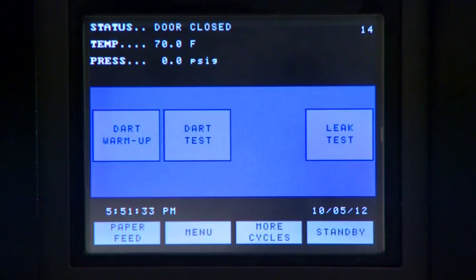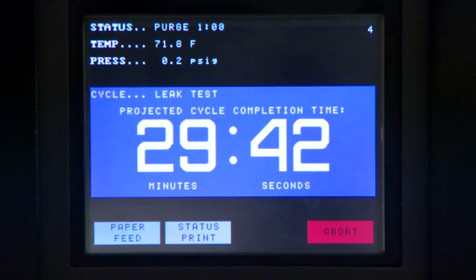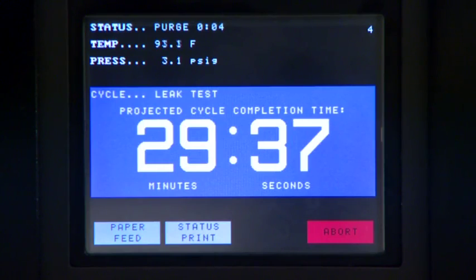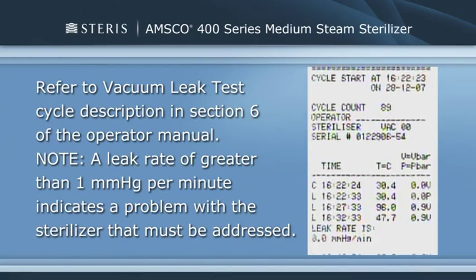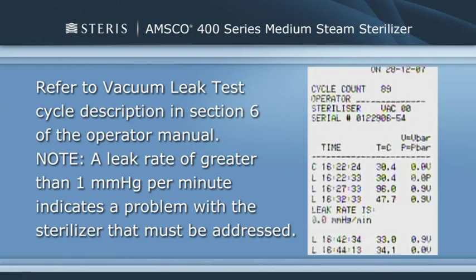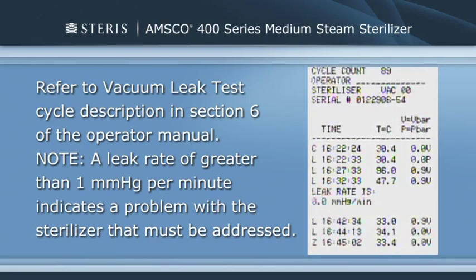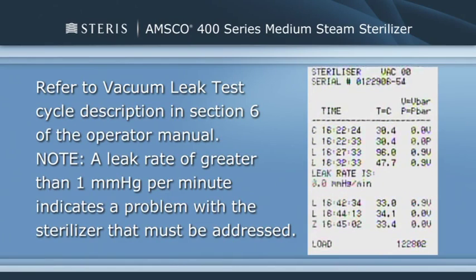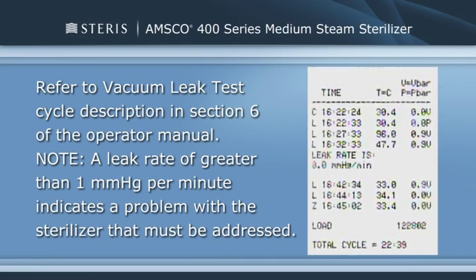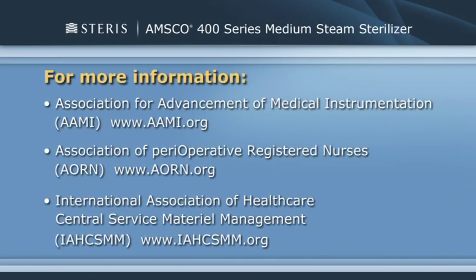The vacuum leak test cycle, which should be run daily or weekly, measures the integrity of the sealed pressure vessel and associated piping to assure air is not being admitted to the sterilizer during the vacuum drawdowns. After running a leak test cycle, a value or leak rate will be printed on the printer tape. This value will help define a trend over a period of time if the integrity of the system begins to deteriorate or allow air to enter the system. For additional information on sterilization standards and practices, STERIS Corporation recommends that you review the guidelines published by industry associations such as AAMI, AORN, and IAHCSMM.